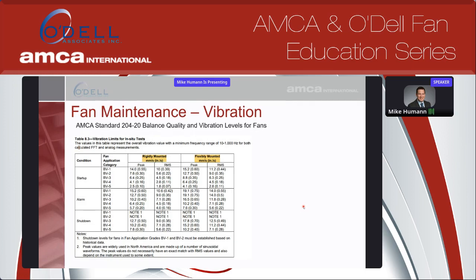So those numbers differ. You'll see the rigidly mounted numbers are lower than the flexibly mounted, because the fan's going to move a little bit more. And you'll see different conditions here with startup, alarm, and shutdown.